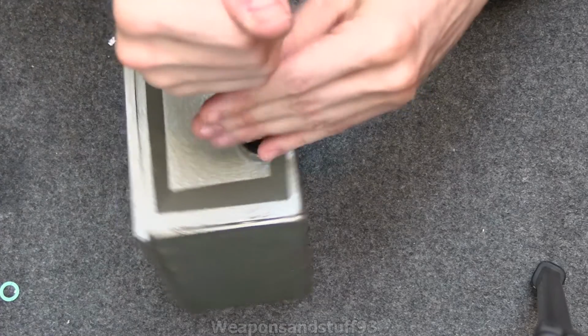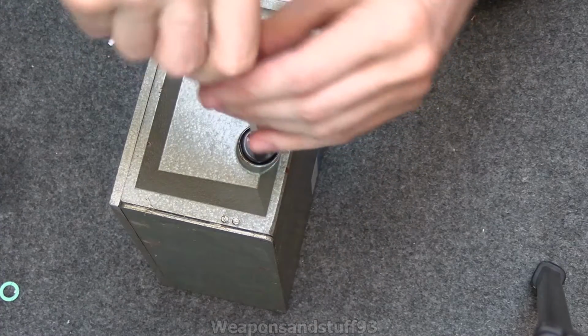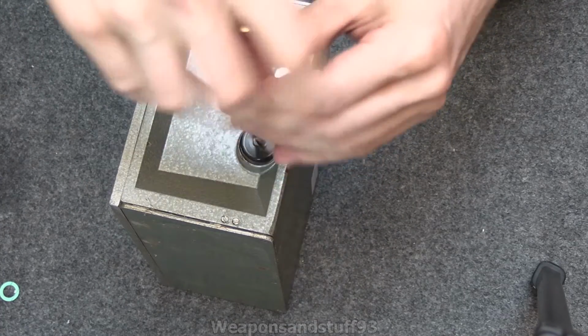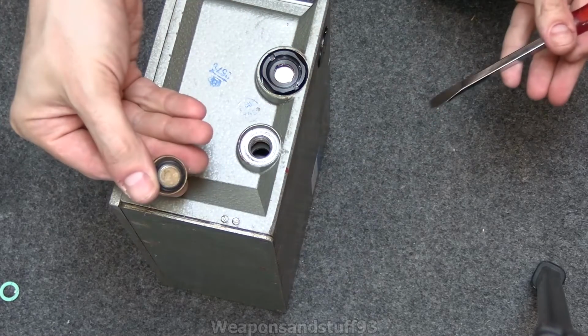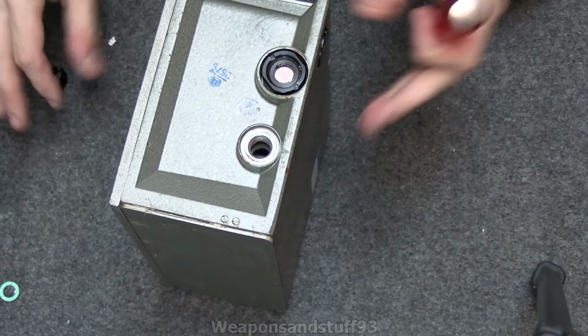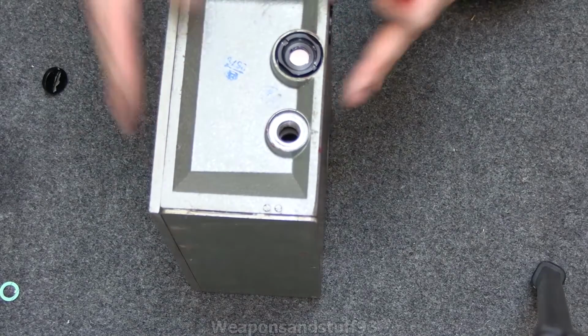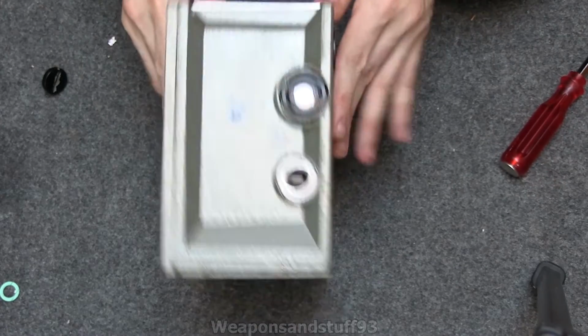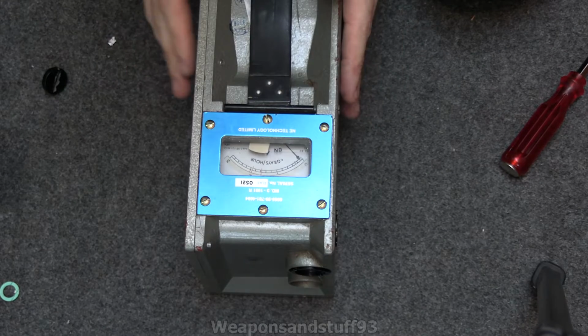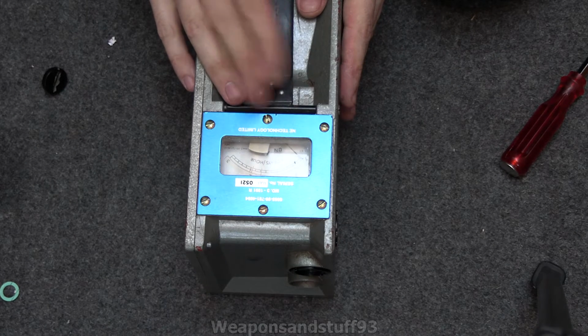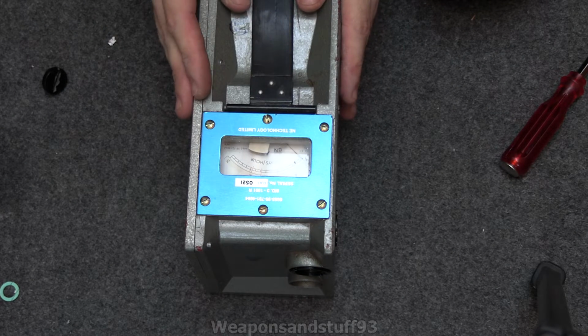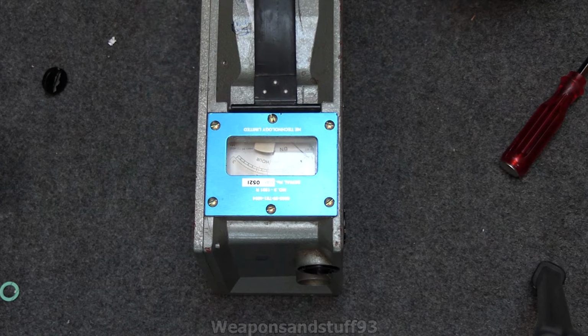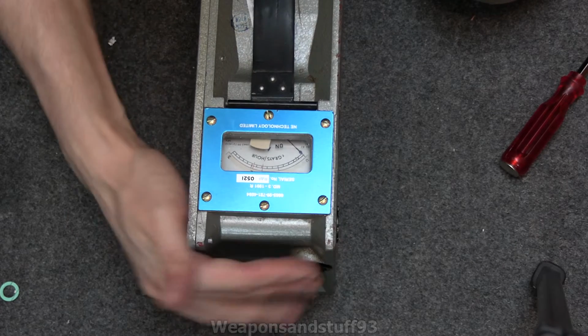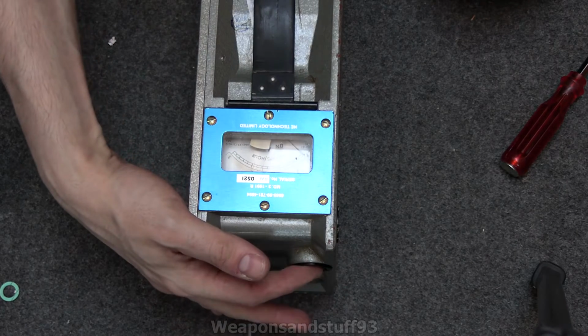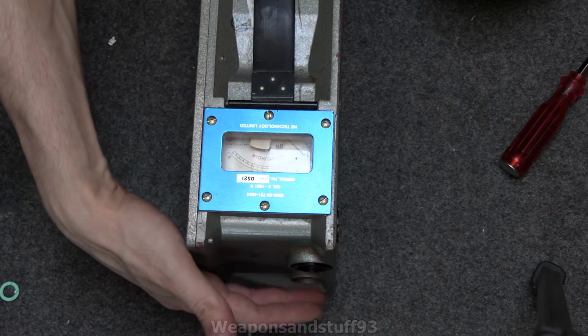So what you do, you unscrew this port, and this is the calibration port, or basically the test port. You get that out, you open that, and that's the test port in there. So that opens the access up to the ionisation chamber. Now what's going to happen is, because that port is open, obviously alpha radiation can enter and therefore mess with the needle. And as I said, I've not got anything handy that's not locked in the safe that I could use this with. But basically what you would do, you just simply get a bit of AM241 or whatever equivalent.